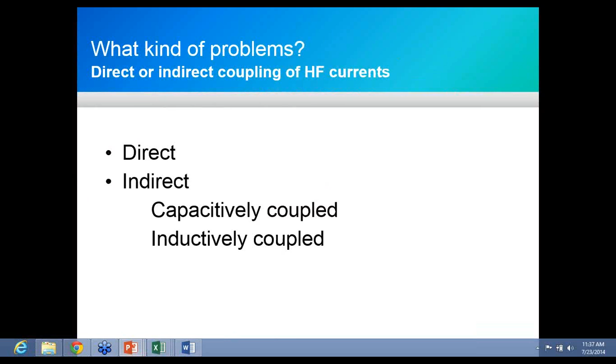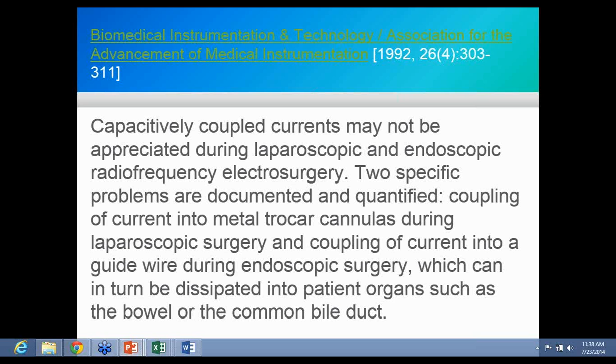So, what is tested? HF output current from the active and the dispersive electrode. You have to test both of these because both of these are conductive paths. Both can produce the unwanted HF leakage. When the tests are done, either the active electrode is left open or the dispersive electrode is left open.